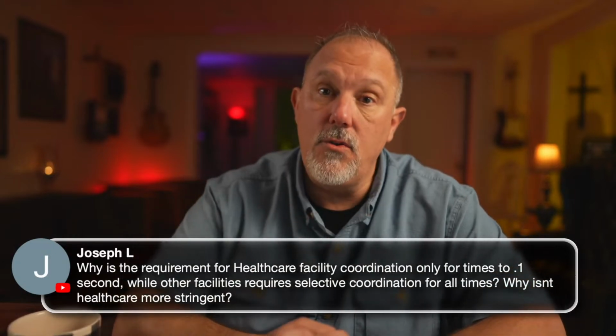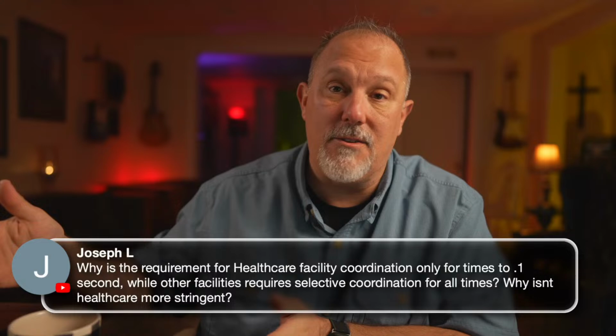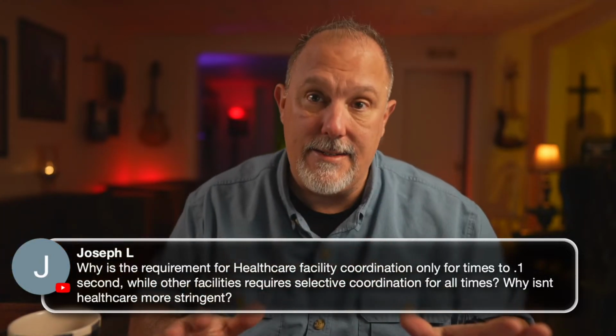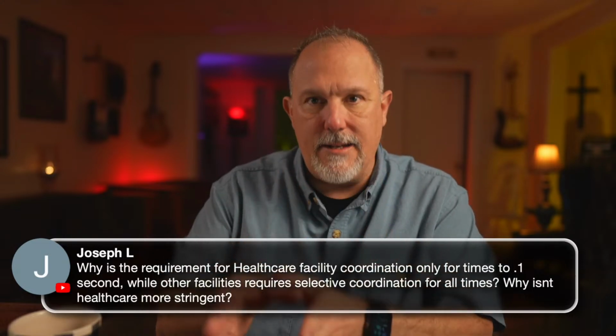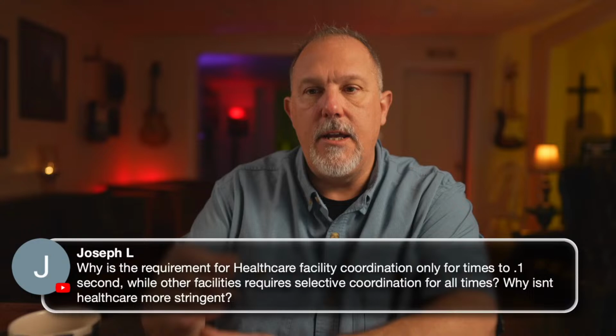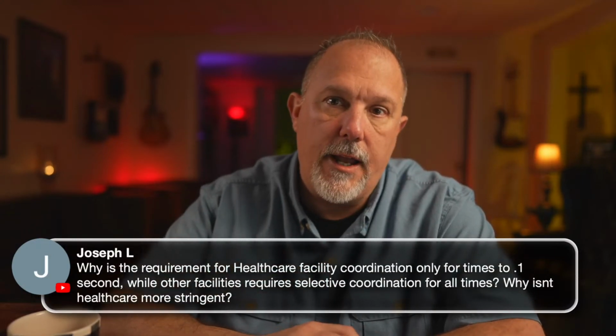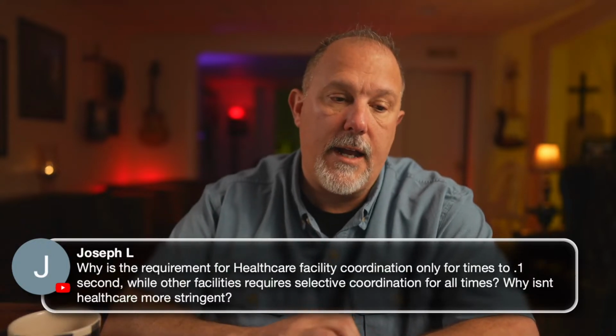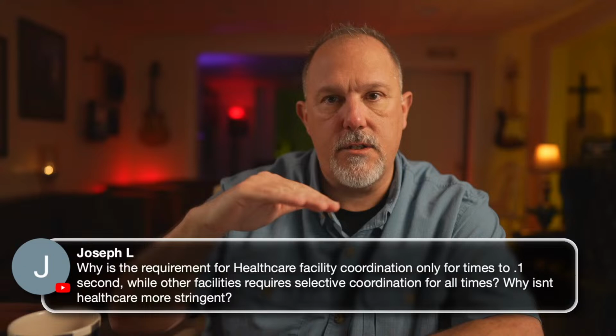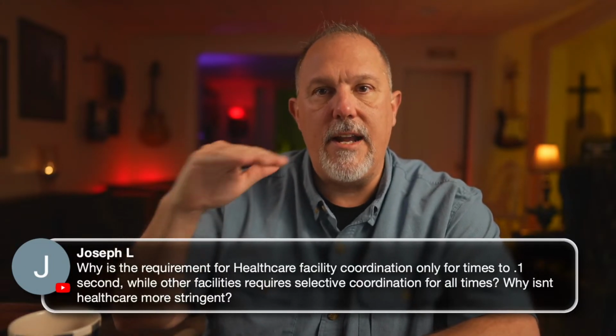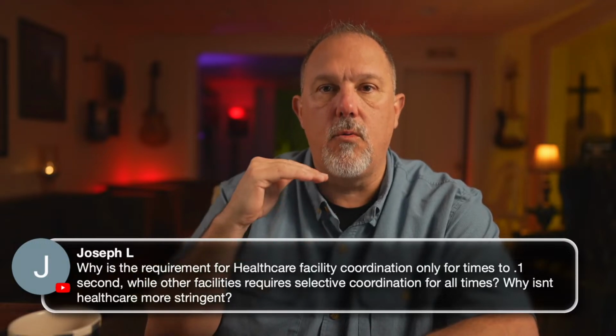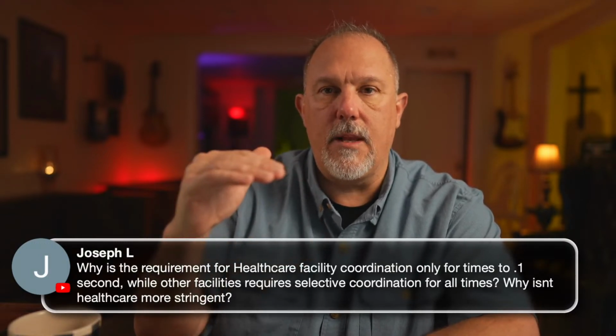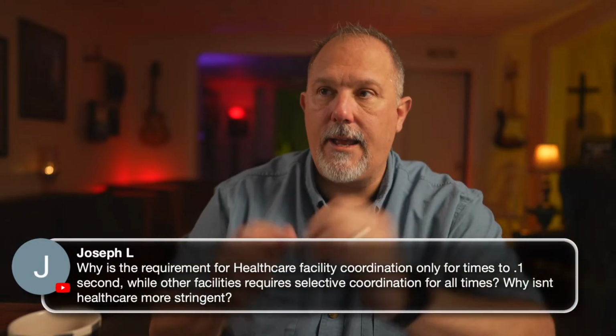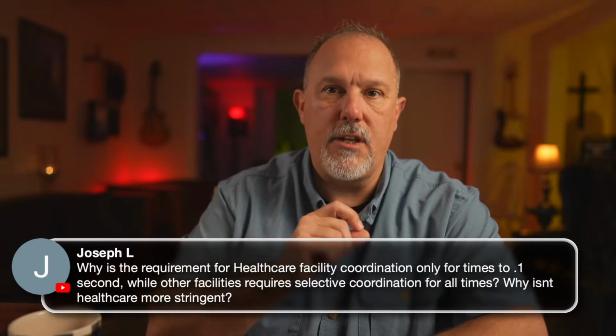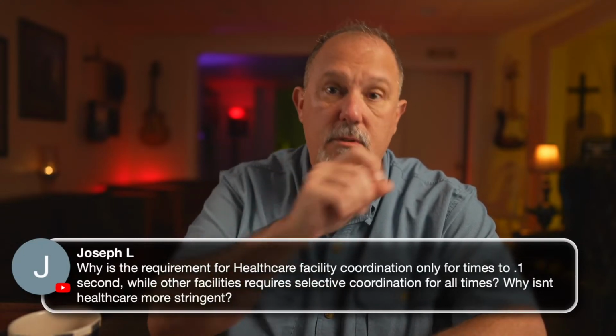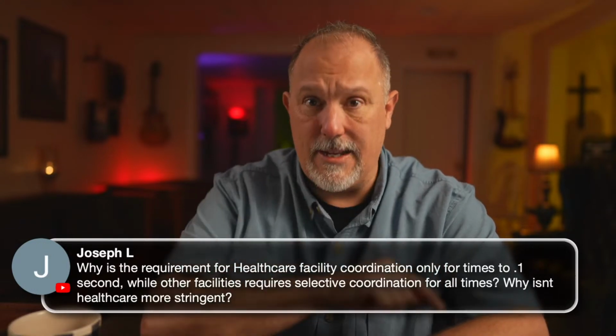I have in the past, and I've used it, not where the code required. If the code requires it in Article 700, 701, 708, that's a done deal. But it's when a client of mine would want a reliable power distribution system, I may go to ground fault currents and make my point to the client that I can get you to a higher level of confidence from a reliability perspective if I ride through and I ensure ground fault currents coordinate. Then I have increased your reliability over ignoring it altogether, and I am not accounting for bolted 3-phase fault current values, which I would argue are less likely in a power distribution system.